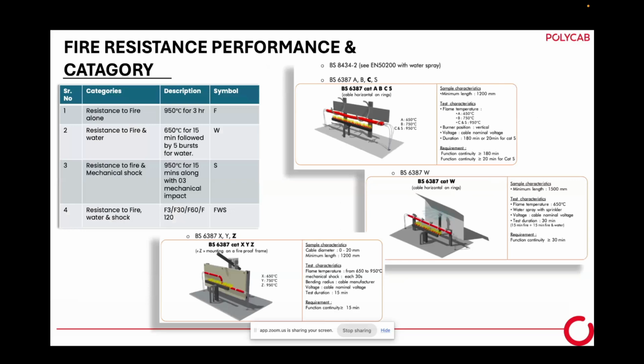So here are some of the testing arrangements we have shown. Since BIS is getting popular, we have written some BIS configuration here. Suppose any customer wants a fire survivable cable and thinks that only fire withstanding capacity matters for his work. Meaning I want a cable where the fire withstanding capacity up to 950 degrees is okay. So he can take a 950-degree cable for 3 hours testing, which is symbolized F.